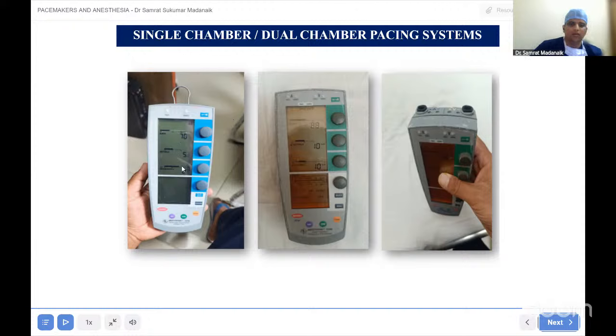So basically it plays the role of the impulse generator, like what we have seen in the permanent pacemakers. So you can set the rate on this, you can set the amplitude, that is the output, and then you can set the sensitivity, that is at what level you want to capture the signals from the endocardium. All these things can be set on this pacemaker. So basically this is a single chamber.